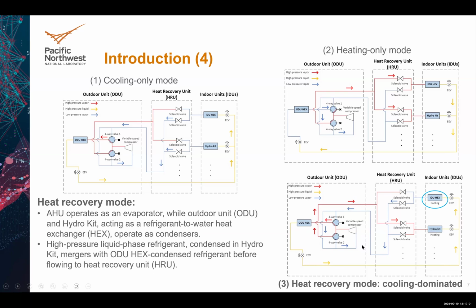So this is the refrigerant cycle for this heat recovery mode. You can see here, I also label the cooling dominant. So basically for heat recovery mode, we have two modes. One called the cooling dominant, another called the heating dominant. Basically depending on the capacity of your indoor terminals.